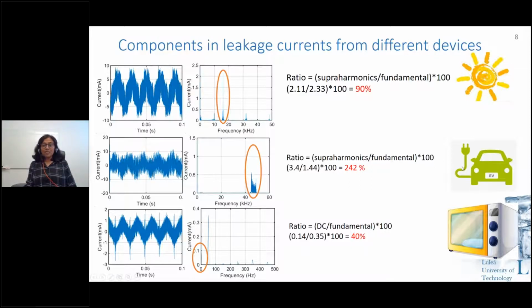Similarly, this is from the EV that we saw. That EV has a broadband emission between 45 and 50 kilohertz, and it is varying in time as well. If I take the ratio of this emission with respect to the fundamental, it is around 242%, so around 200%. So we can see that it is mostly the high frequency emission which the PE current is composed of.